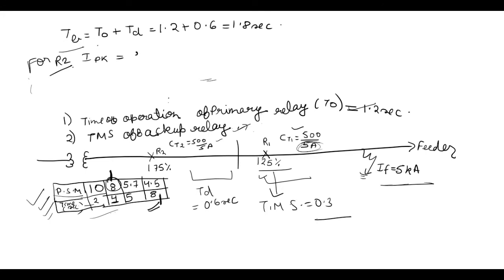Percentage setting of relay. So percentage relay for R2 is 175 by 100 into CT secondary current which is again 5 ampere. So it is 8.75 ampere. And now we are going to find PSM which is fault current. Fault current is 5000 upon pickup current which is 8.75 ampere into CT ratio which is 500 upon 5. So PSM is equal to 5.7.